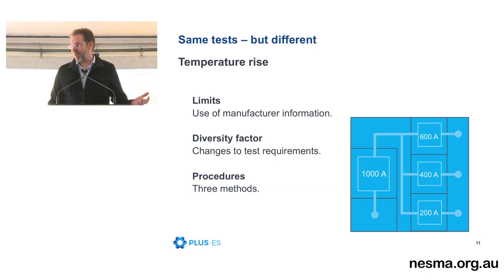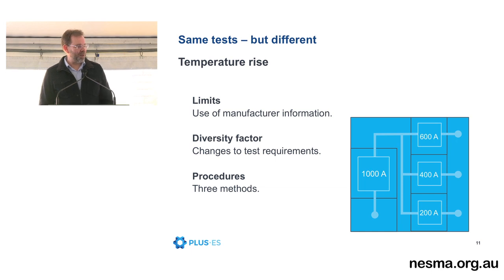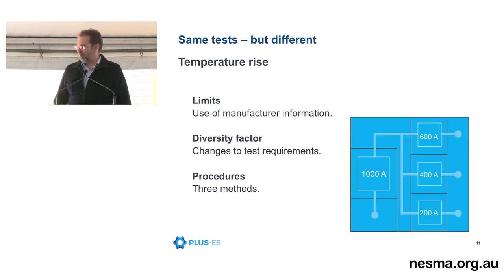Really, it's a 600 amp outgoing unit, but we're still going to call it an 800 amp outgoing unit with a diversity factor of 0.75. So on your certificate or your test report, it still says 800 amp outgoing unit, but it can only actually run 600 amps continuously. I'm talking, this is in a temperature rise test. So there you go. It might not become obvious when you look at the certificate, 800 amp, and you see the diversity factor written below. So that circuit breaker never actually experiences 800 amps continuously, but it's still called an 800 amp unit.